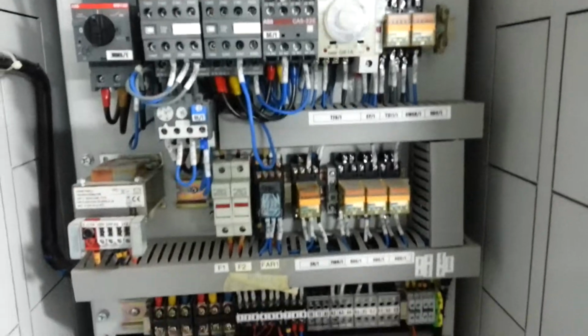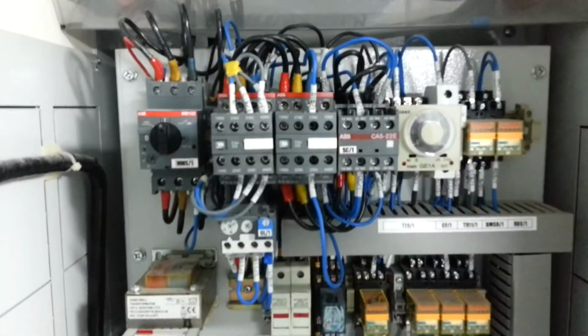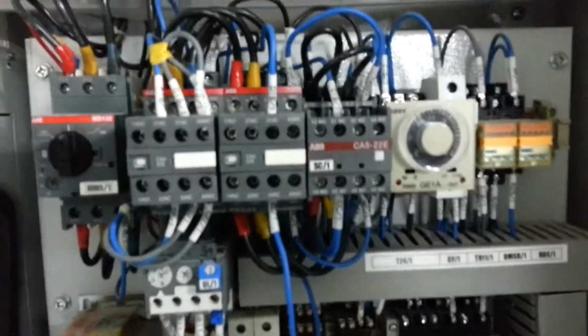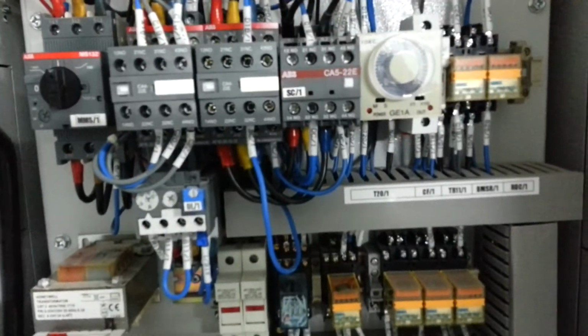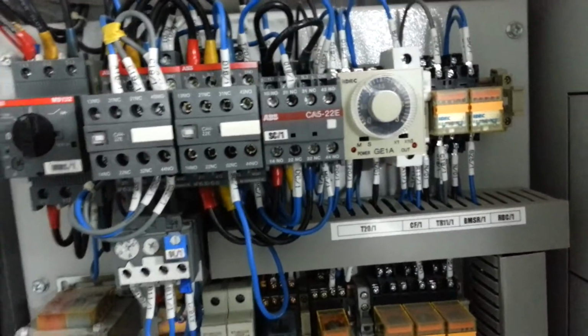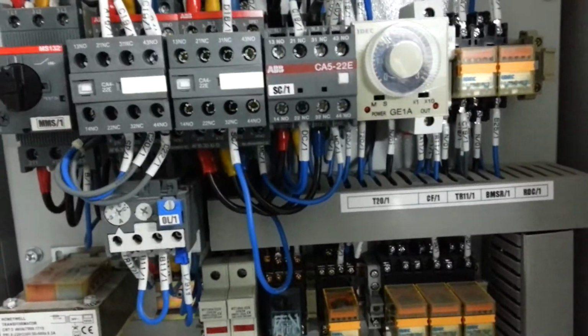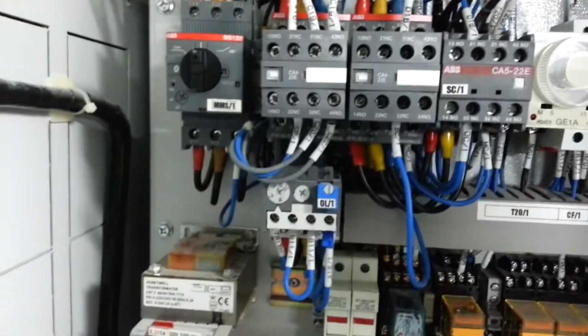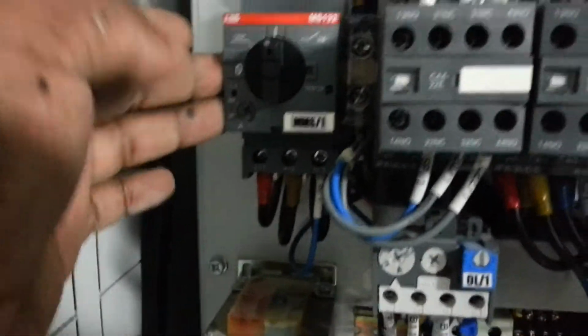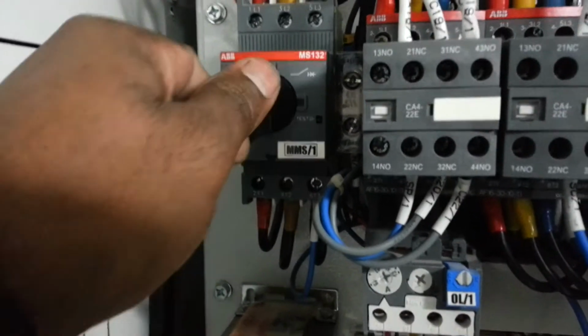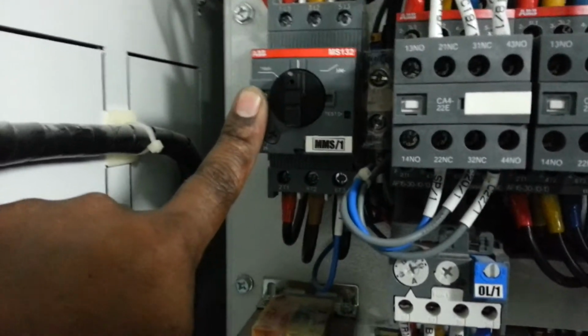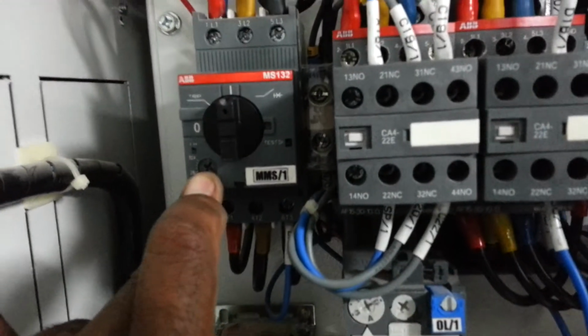Here is the panel board for HU. This is also a star delta motor, around 40 HP, 45 HP like that. Here you can see there is a switch. This is a manual motor switch, which means we can manually turn off the motor, or if there are any high amps or a short circuit, then it will trip. This is the same as breakers, and here we can adjust the running amps.